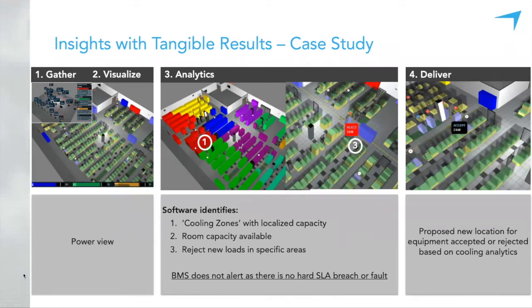In the center, we're looking at a very important piece of the analytics engine, which is the zones of influence. And the zones of influence allows us to associate each particular rack with the cooling unit that supplies it. And this is a time series piece of analysis that allows, over a significant period of time, the temperature variations of each particular rack to be located and associated with each particular air handling unit. And they form patterns that tell us the relationships. And we use this extensively to work out, for each particular zone, how much load there is in each zone associated with each air handling unit.